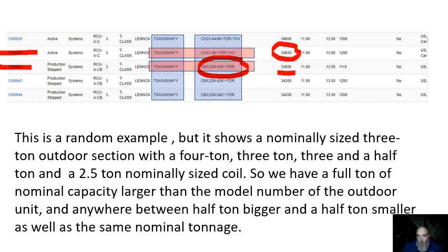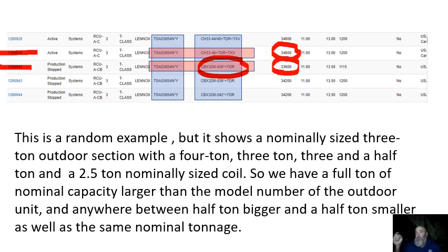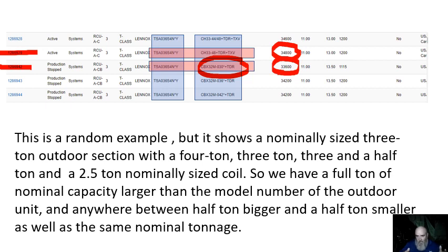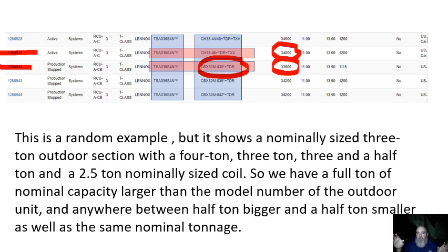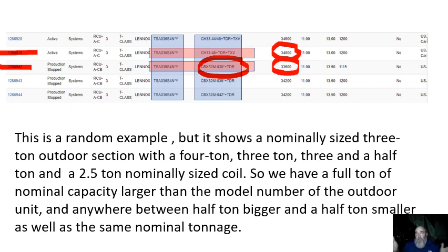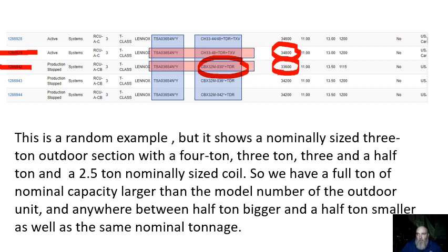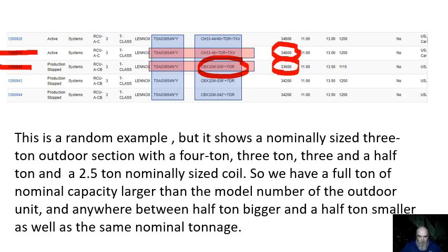But I don't care what the nominal number is because it's irrelevant. If you look at the total BTU output and compare these, they're within 1,000 or so BTUs at a specific airflow. But to say that you can't put a smaller coil in is inaccurate. If you're going to say you're matching a 3 to a 4-ton coil, there's no such thing.